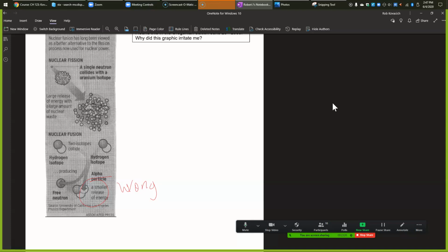Well, you said it. The way we have it set up, no. Remember what the temperature of the primary coolant was? Do you remember the primary coolant was pressurized to 2,000 pounds? Why was it pressurized to 2,000 pounds? Because the water temp was 525 degrees. So it didn't boil? It didn't boil. So it's way hotter than boiling water. We're just using it to turn water into high pressure steam. But regardless, the water temp is 500 degrees, and there's a tiny bit of uranium compared to the amount of water. And we all know water is difficult to heat because of its specific heat.